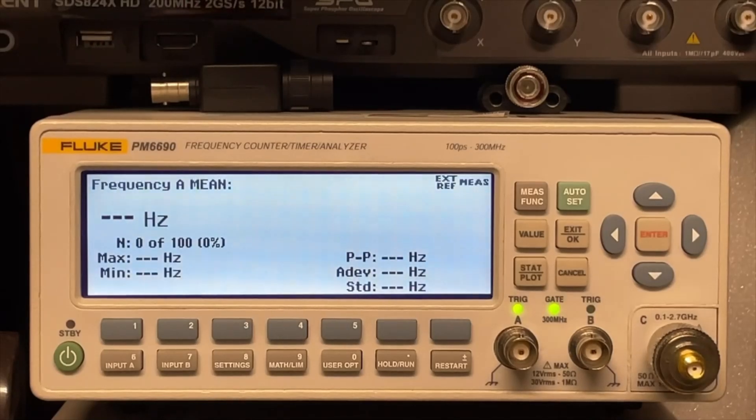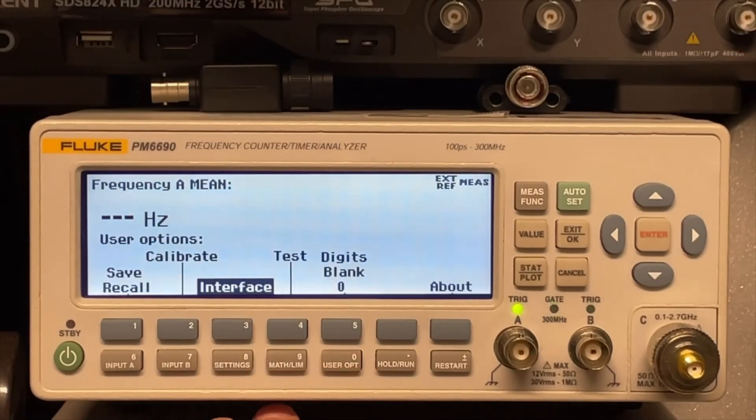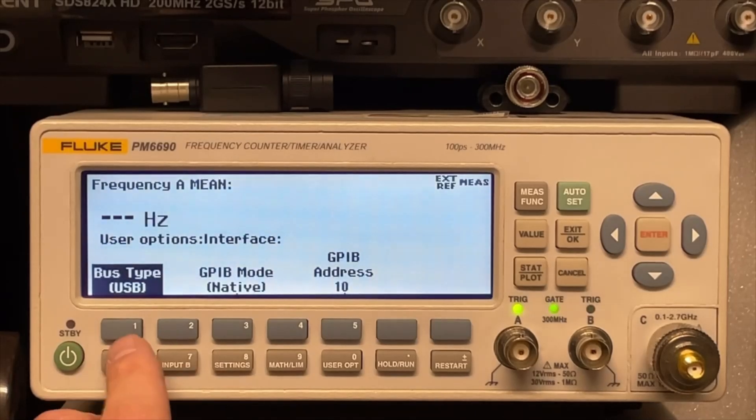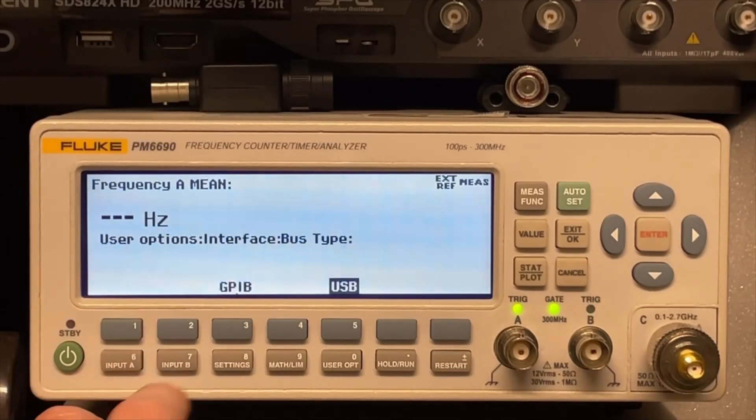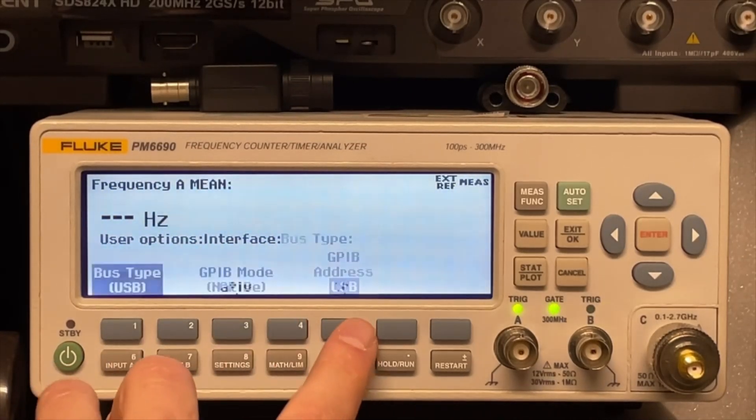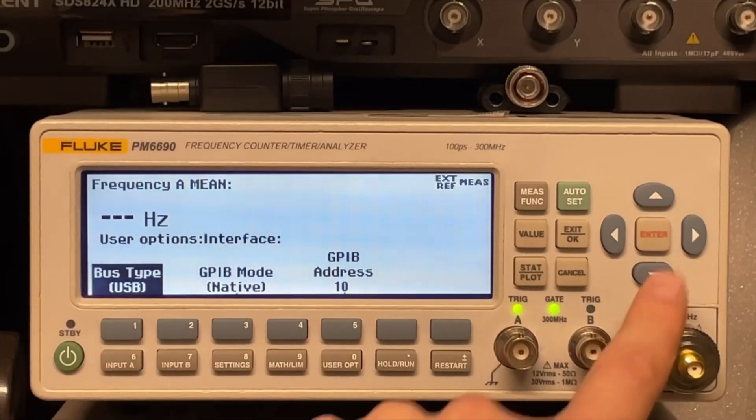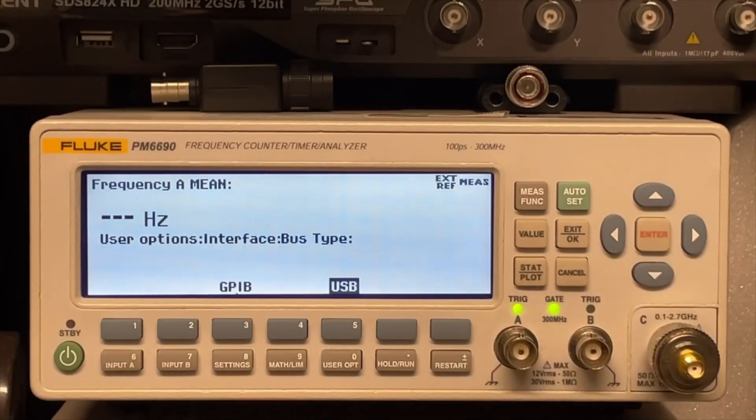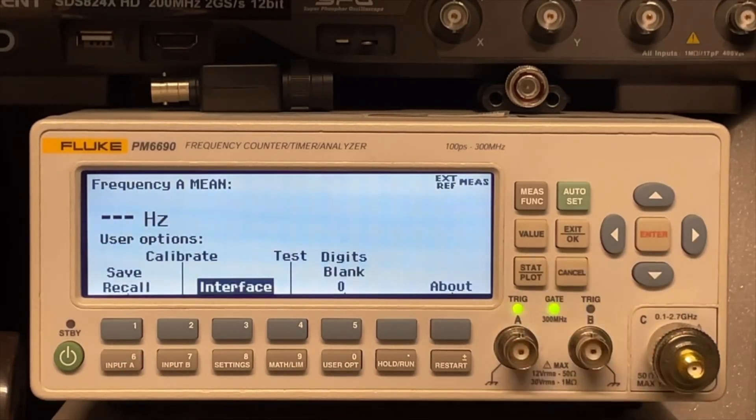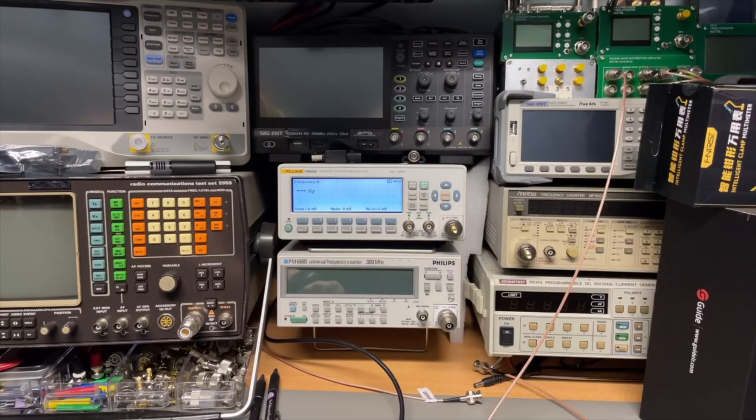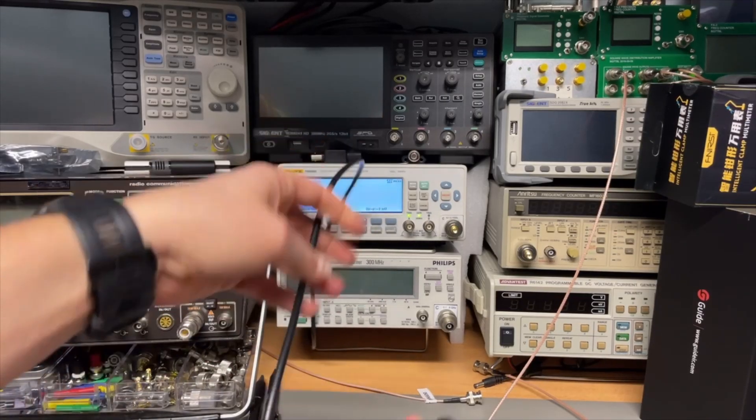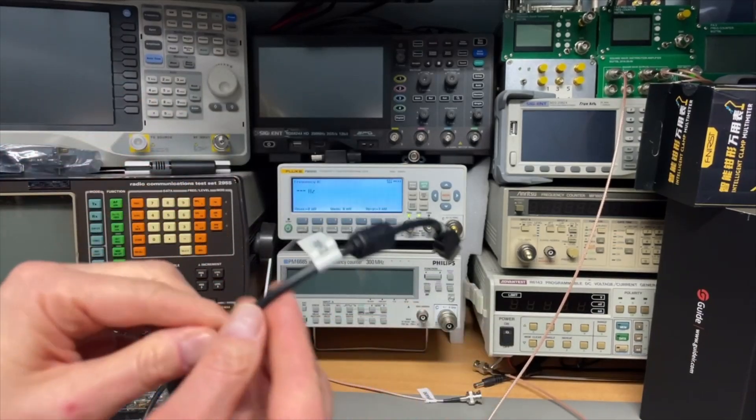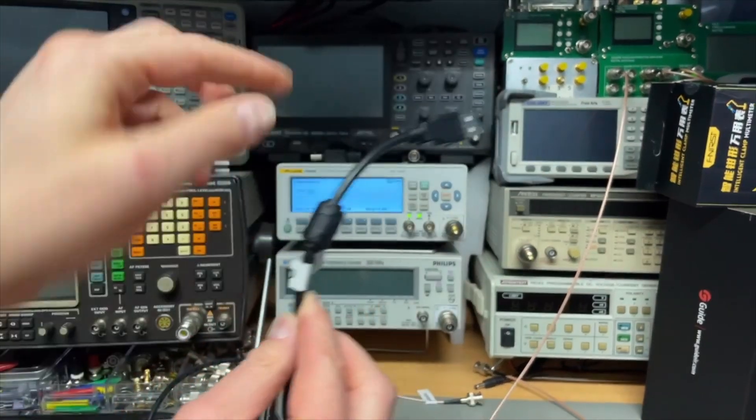I think by default the device is set to GPIB. So we go to user options, interface, and then we set it to USB here. You can switch here GPIB or USB and then okay. Now it's set to USB. We go out. I already connected the USB cable. I have here with a choke on it.